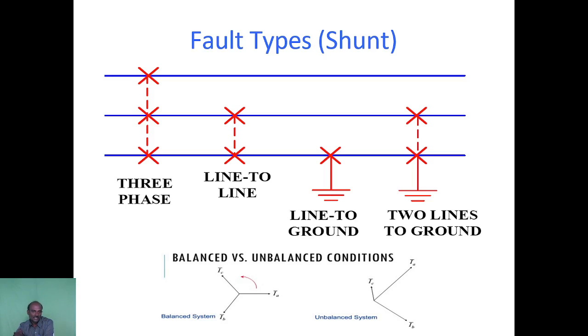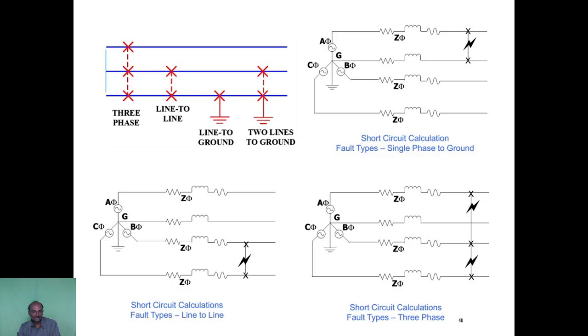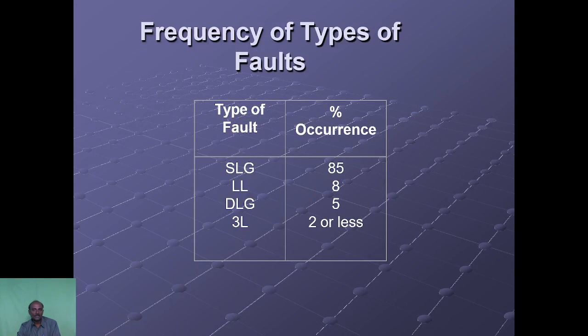Line to ground faults, line to line fault, that is short circuit between any two lines, three-phase faults, or two-line to ground faults. Symbolically, we can represent the various faults. Then the frequency of types of faults, based on the occurrences. The major percentage of occurrence of fault is due to single line to ground fault. So 85% are single line to ground faults. That is the short circuit between any one of the lines and the ground.